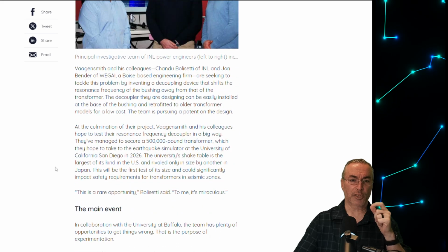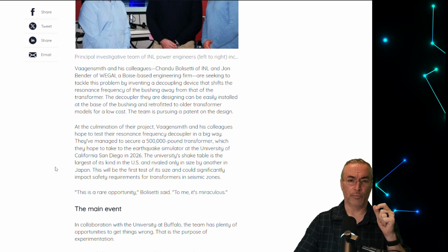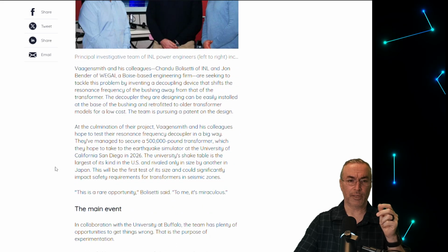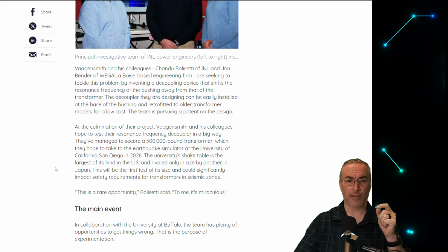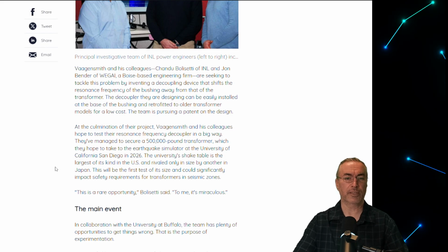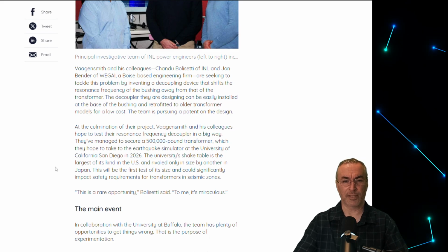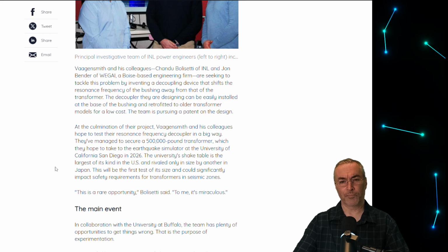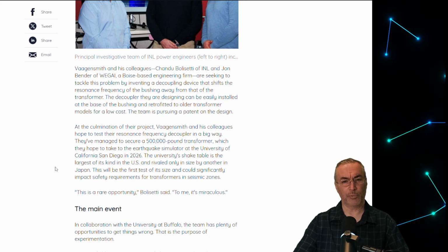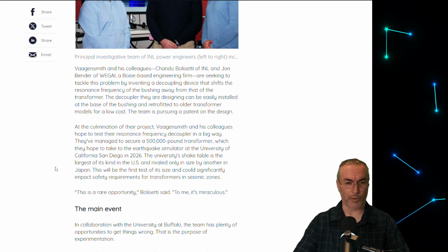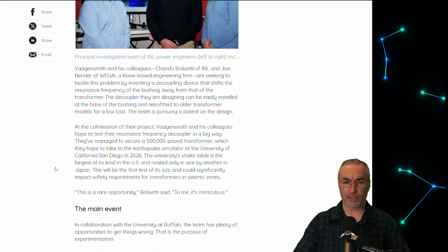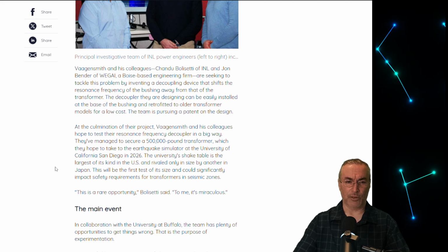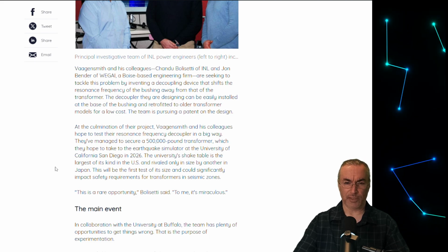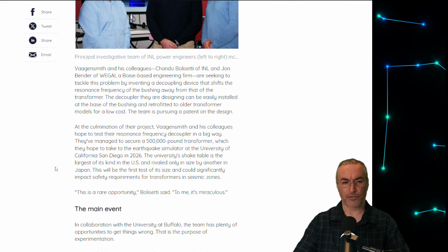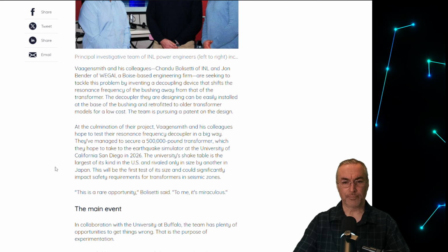So Vaagensmith and his colleagues, Chandu Bolisetti of INL and John Bender of WEGAI, a Boise-based engineering firm, are seeking to tackle the problem by inventing a decoupling device that shifts the resonant frequency of the bushing away from that of the transformer. The decoupler they are designing can be easily installed at the base of the bushing and retrofitted to older transformer models for a low cost.